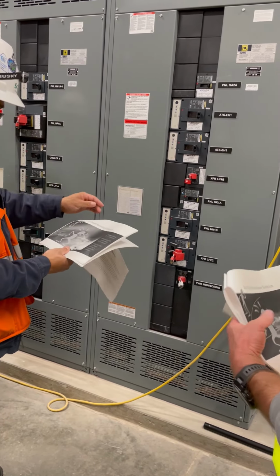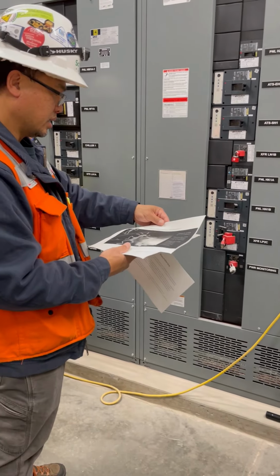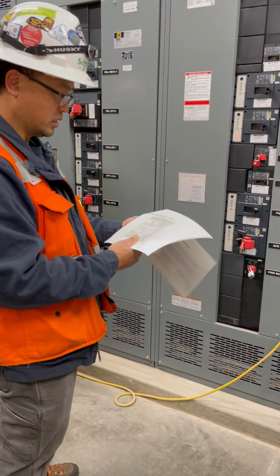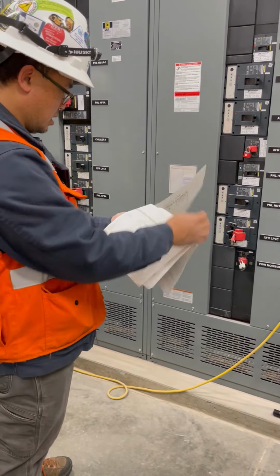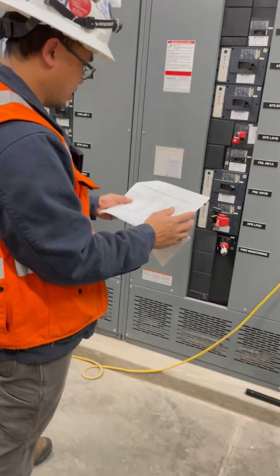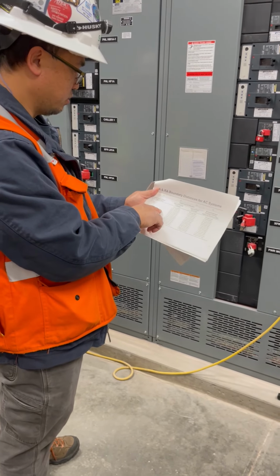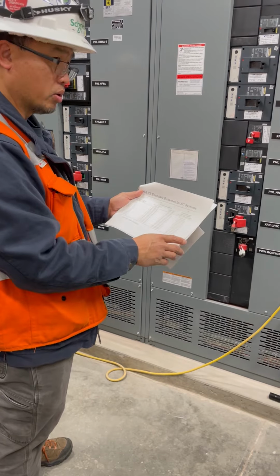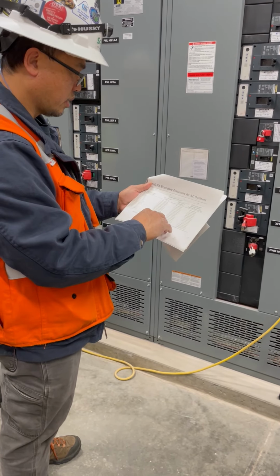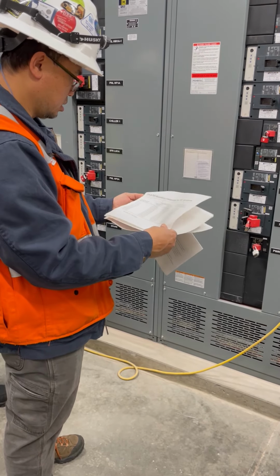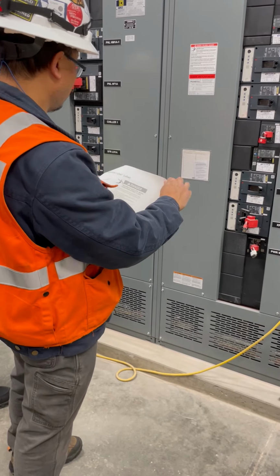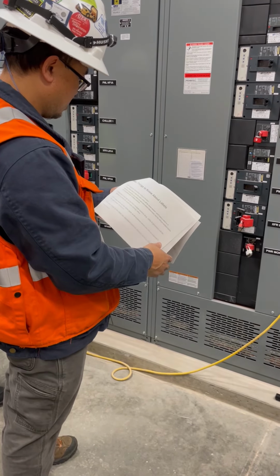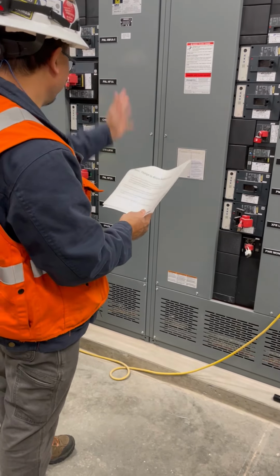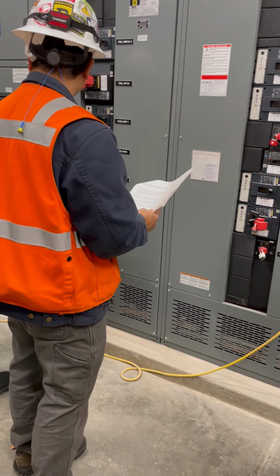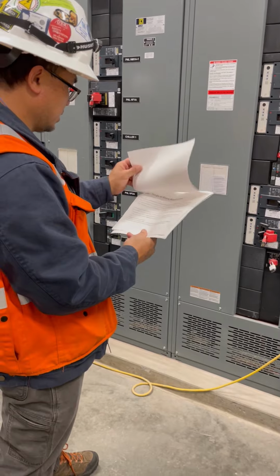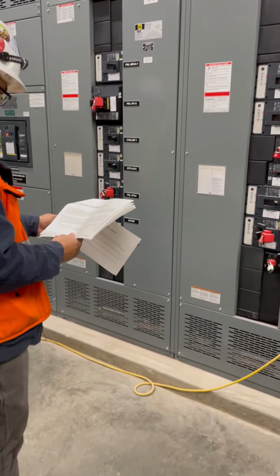The next page shows you what the arc flash boundary is, and this is just the label. This is directly taken from the NFPA 70E book, which gives you, depending on the voltage level, the limited approach and restricted approach, and they're fixed. The higher the voltage level, the larger the limited approach and restricted approach boundaries. That's just general information. We put a label on each vertical section, so if you notice one here, one there, every one of those has a label.